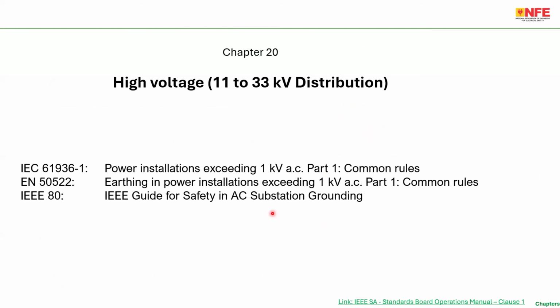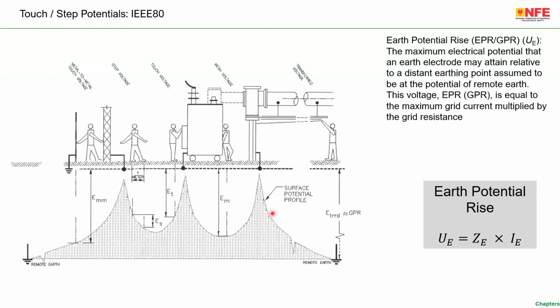Now coming to the high voltage distribution system, I'm sure a lot of you are using the IEEE standard, and most of you know the definition of these parameters. What is GPR, ground potential rise, which in the IEC standard we call EPR, earth potential rise, which is nothing but the UE, the term actually used in the standard. UE is the earth potential rise, which is equal to ZE times IE. ZE is the impedance of the earth electrode. IE is the current which is flowing to the earth electrode.